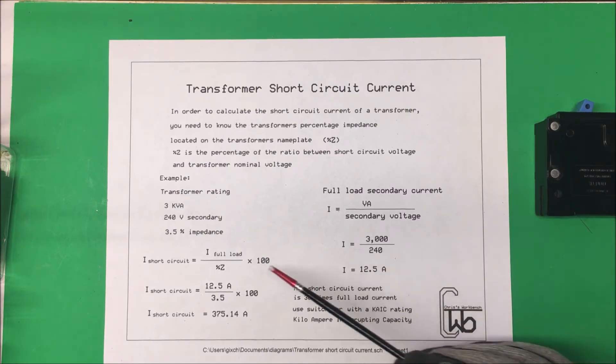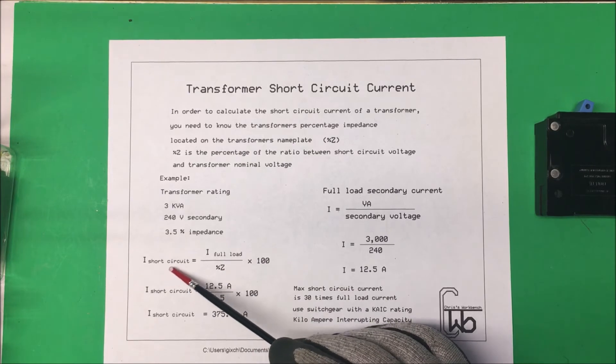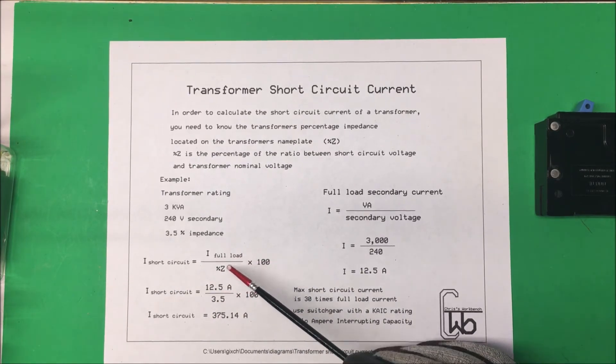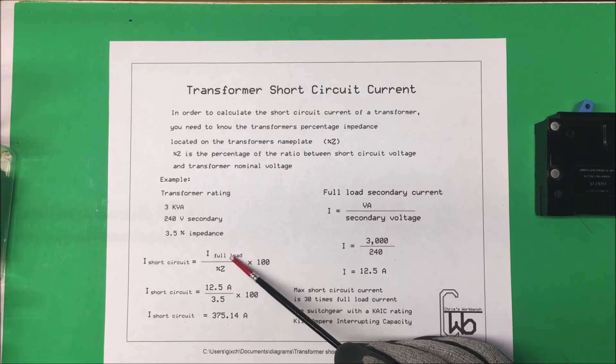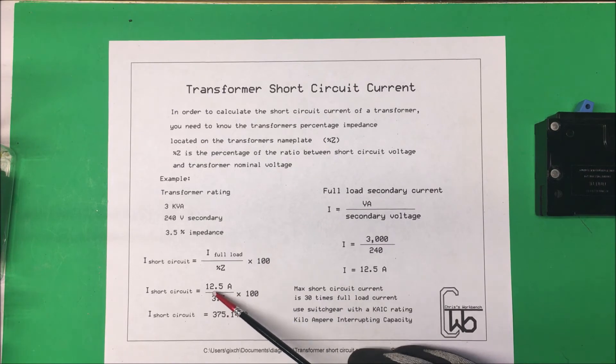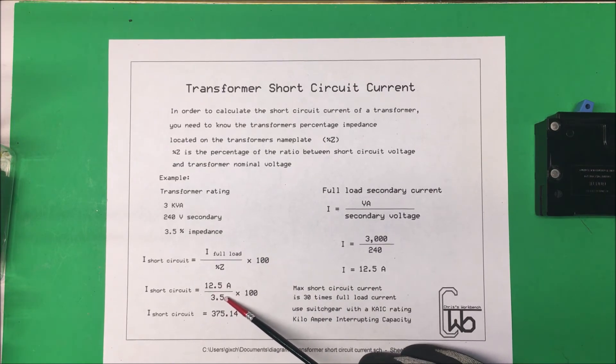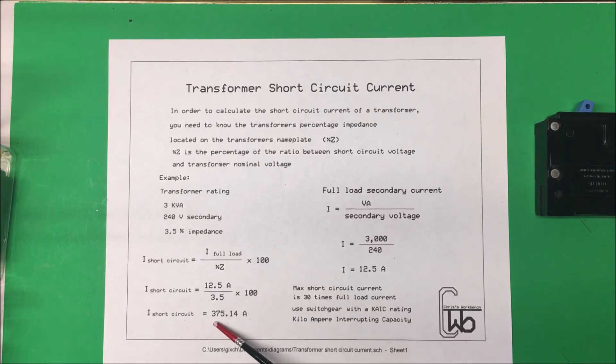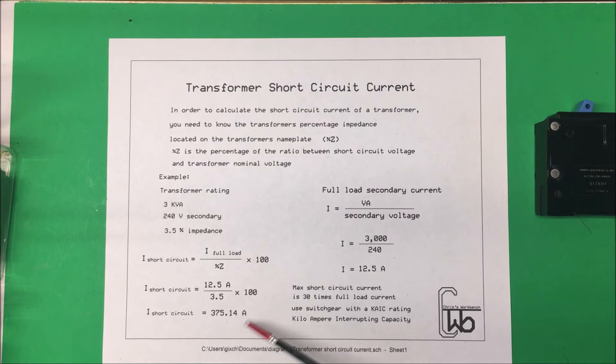Now if we short that out to find our short circuit current, we take our full load current, which is our 12.5 amps, and we divide that by percentage impedance and we times that by 100. So we got our 3.5 into our 12.5 times 100, so that comes out to 375 amps if we short it out.